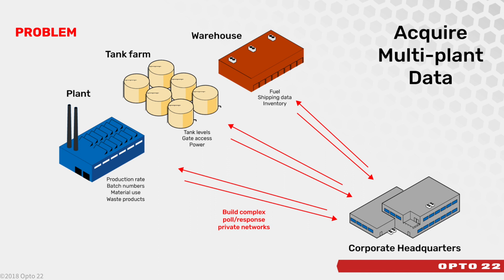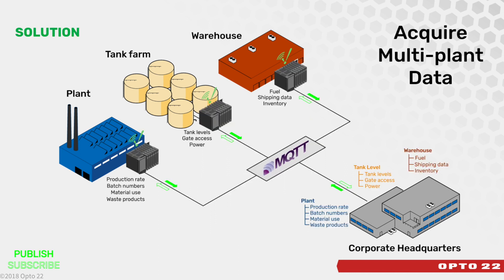So what to do? Deploy an MQTT publish and subscribe architecture so each location publishes their own nominated data tags to their MQTT broker securely over an outbound persistent connection — either over cellular, Ethernet, or even the Internet. All security is managed in one place, the broker, so IT can get a handle on the entire system quickly and easily. This scenario is also applicable to SCADA systems — it sure beats building out proprietary SCADA radio networks. And that takes us now into our live demonstration where I'll show you how all the pieces come together.